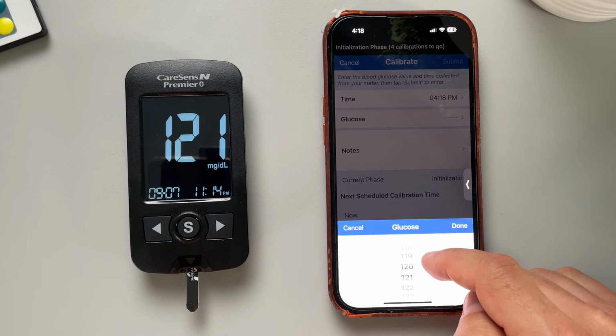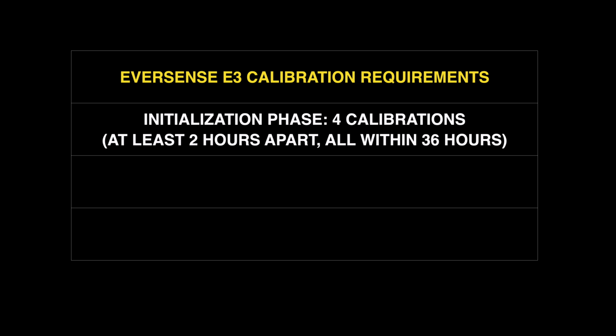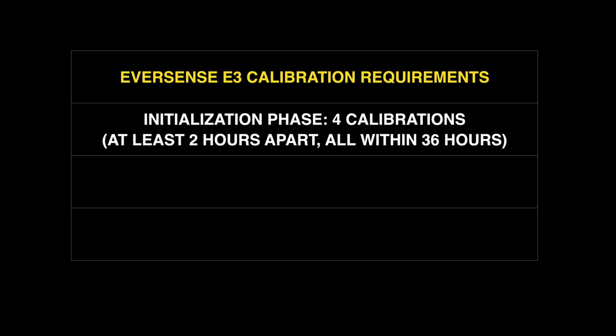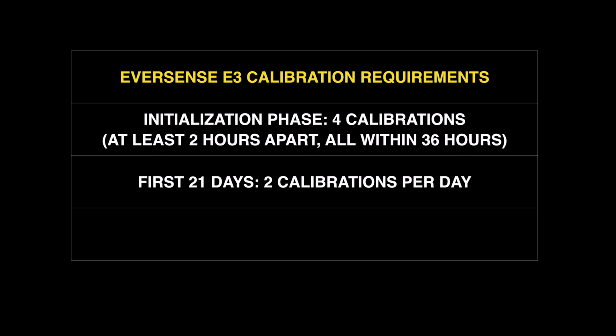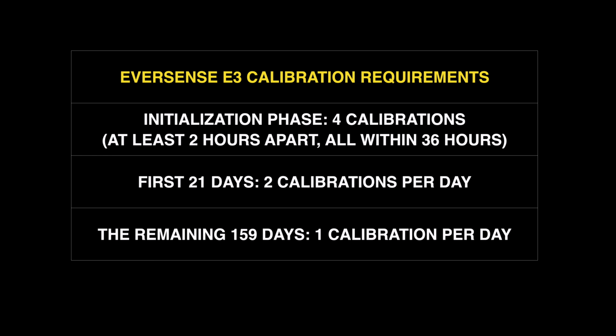During the initialization phase, I actually had to complete 4 calibrations, each at least 2 hours apart, all within 36 hours. It probably goes without saying that I didn't love the initial calibration cycle, but once I got through it, things got a lot easier. During the first 21 days, I had to calibrate twice a day, and for the remaining 159 days, I only had to calibrate once a day.